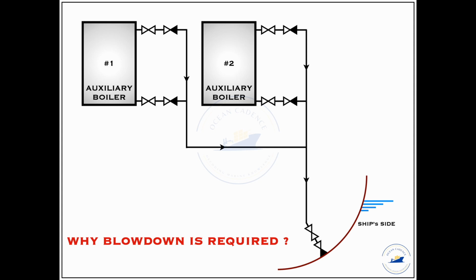That is the removal of the existing water that is there in this system and addition of new water subsequently with new chemical dosage so as to maintain the boiler in a healthy condition. Now, there can be other occasions also where salt contamination can occur, such as leaks inside the tubes for the atmospheric condenser, or maybe leak inside the steam lines that are being circulated through the bunker tanks or other big tanks. And these leaks can be in the form of certain cracks or certain contamination in the open system.